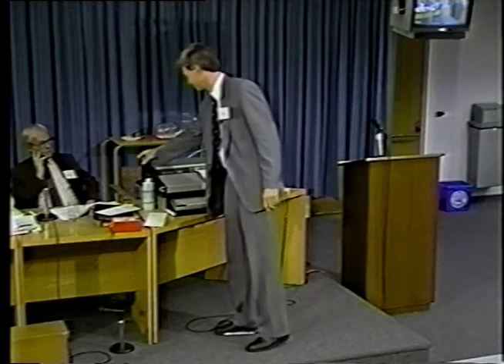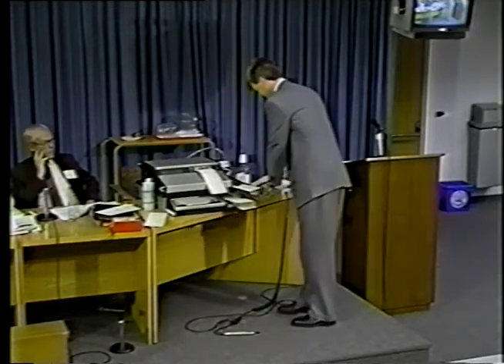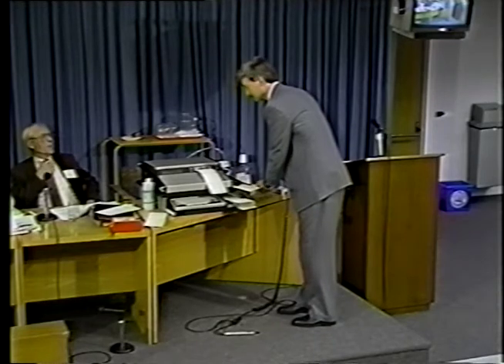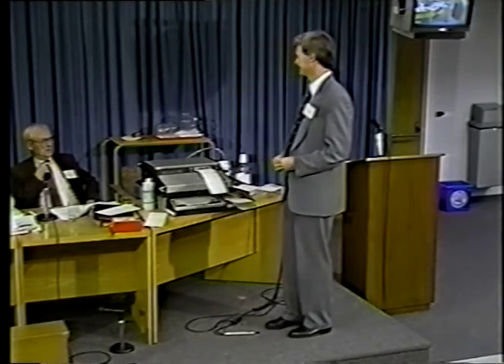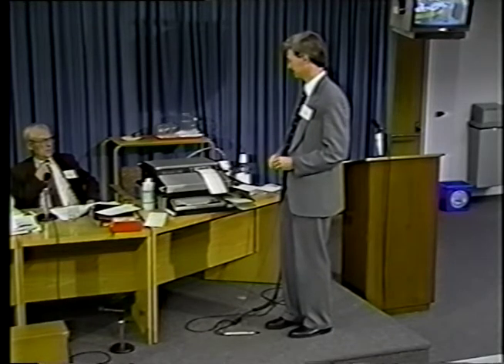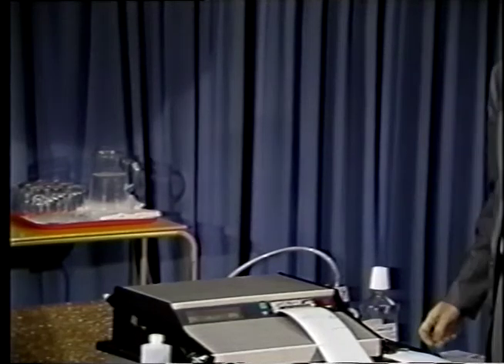Okay, now we're ready. Air blank again, the same procedure is followed. It still does the air blank going in, and then it'll do the 10 internal checks, and then it'll do the calibration check, which should be 100 plus or minus 10, and then it'll be ready for the subject test. The advantage of the calibration check here is you see the sample is recirculated, so virtually there's no loss of alcohol when you're doing an alcohol standard test. It has an option, and again, it's totally automatic. Once the data has been entered, basically the person has just pressed the Start Test button.